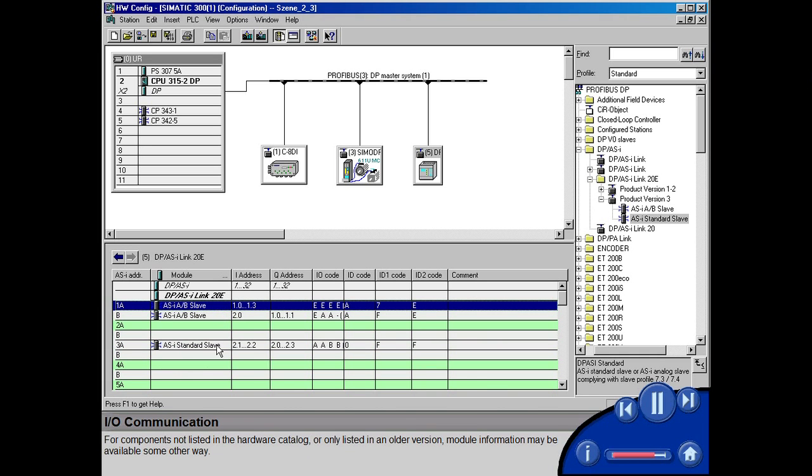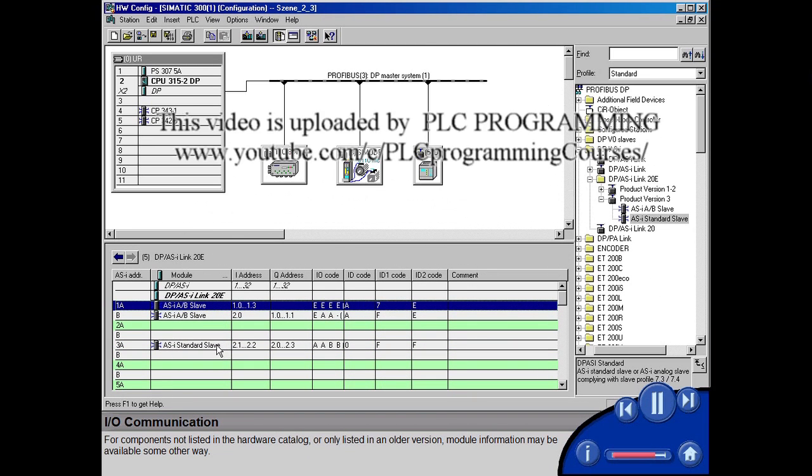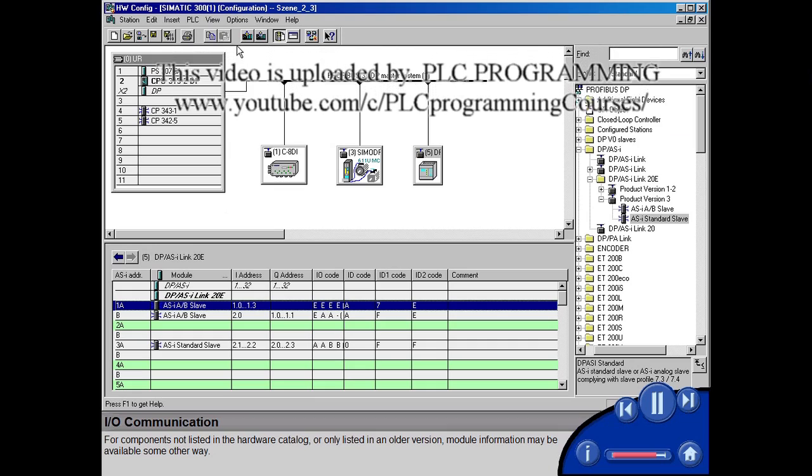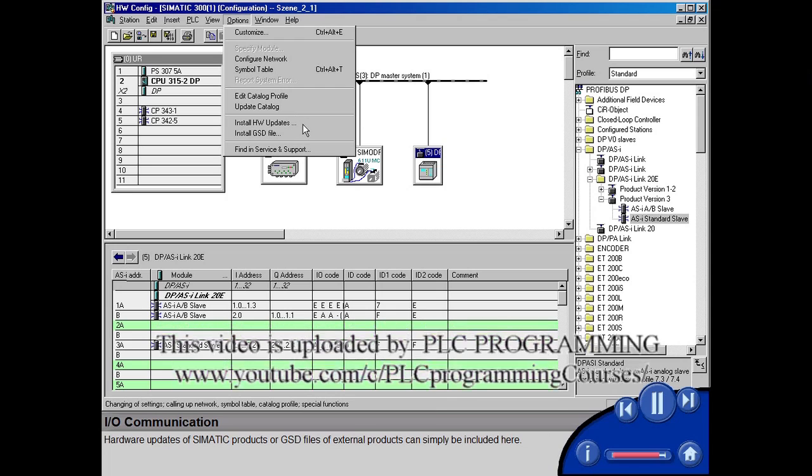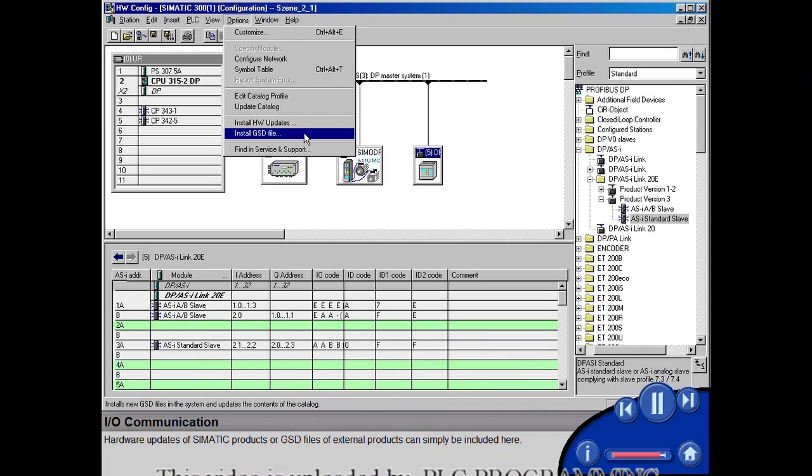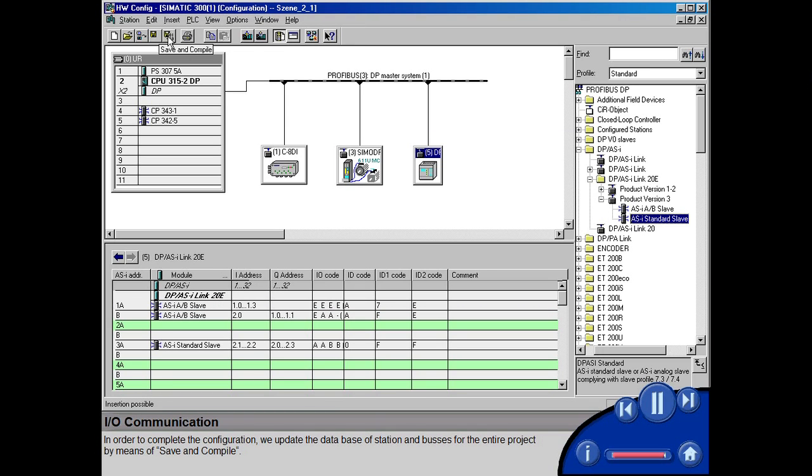For components not listed in the hardware catalog or only listed in an older version, module information may be available some other way. Hardware updates of SIMATIC products or GSD files of external products can simply be included here. In order to complete the configuration, we update the database of station and buses for the entire project by means of save and compile.